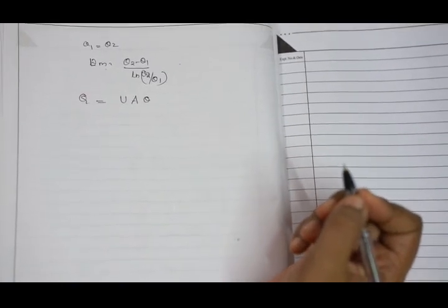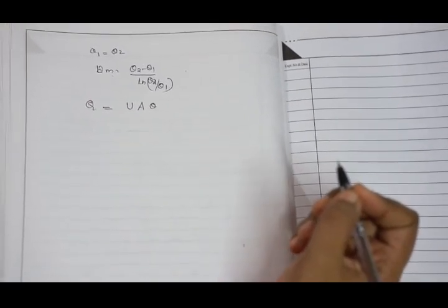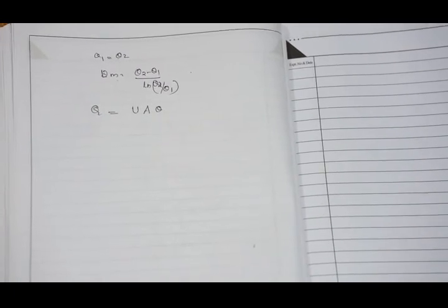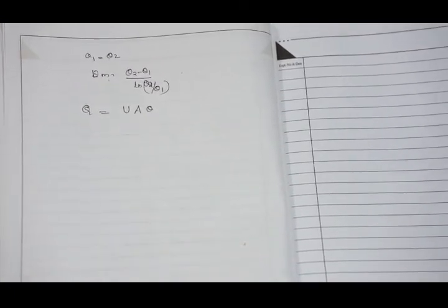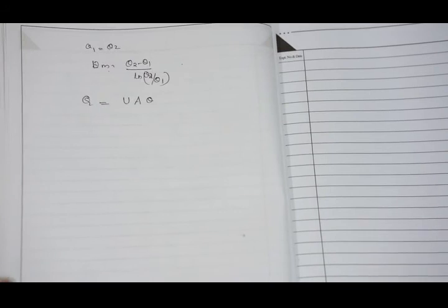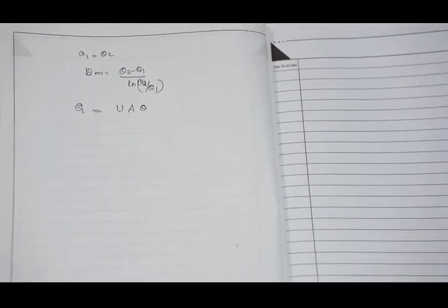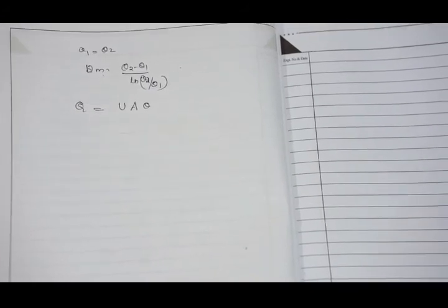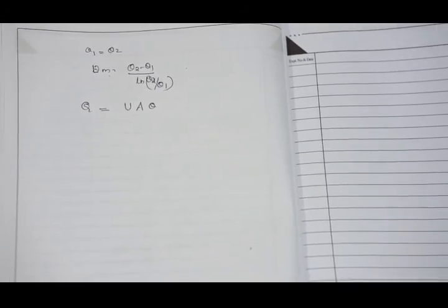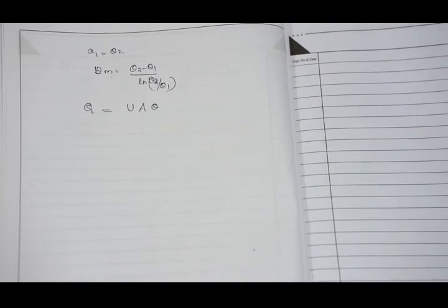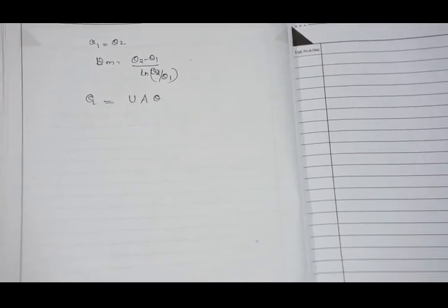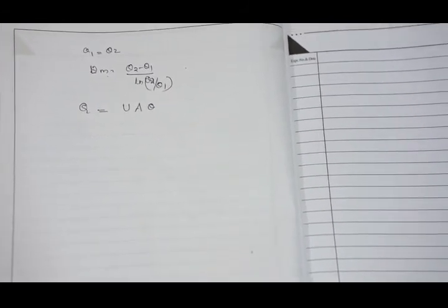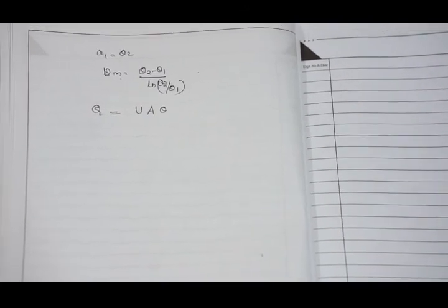Theta m for a counterflow heat exchanger is always greater than that for the parallel flow unit. Hence, the counterflow heat exchanger can transfer more heat than the parallel flow one. In other words, a counterflow heat exchanger needs a smaller heating surface for the same rate of heat transfer. For this reason, the counterflow arrangement is usually used.